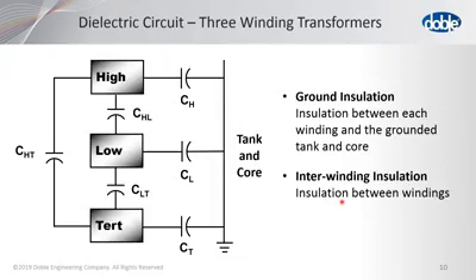So all the insulation from the high voltage winding to ground, we will identify as CH. We used to call it CHG, but we dropped the G because it's just understood. The low to ground, of course, is called CL, and between the tertiary and ground is CT.